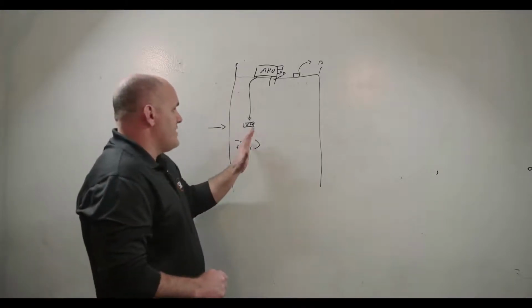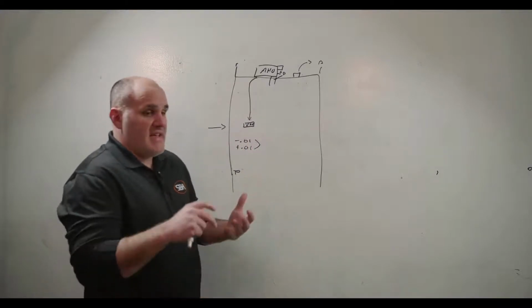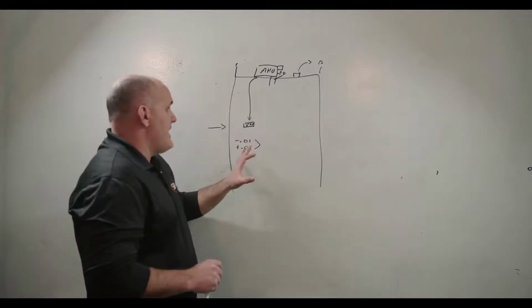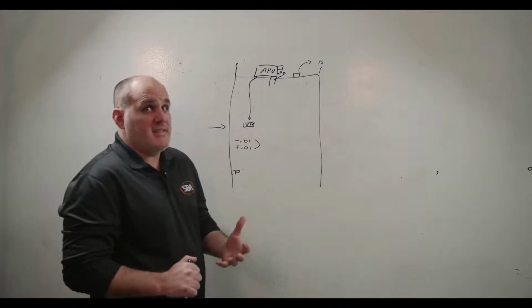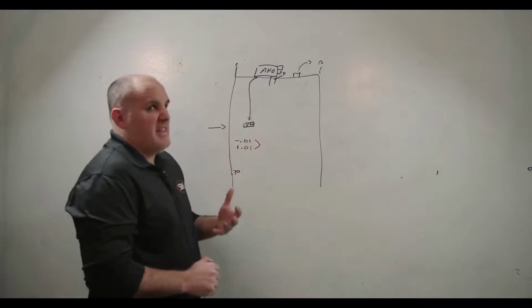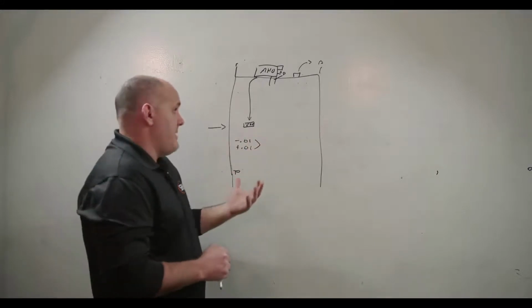Those are where you're typically going to have to use TSI pressure monitors within the space and outside the space to detect if the space is positive or negative. And in that case, you'll typically be using a Phoenix Venturi valve VAV system, something similar, and you'll be driving that using typically volumetric matching or volumetric offset in order to drive pressure in the space.